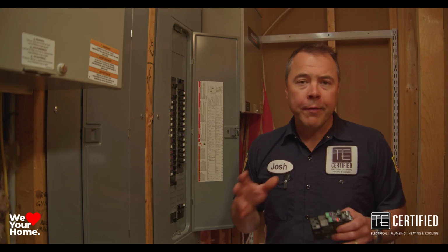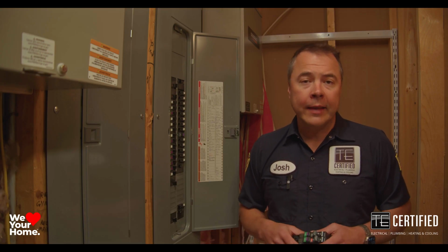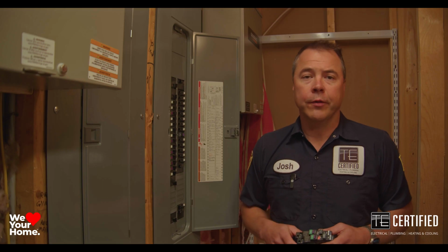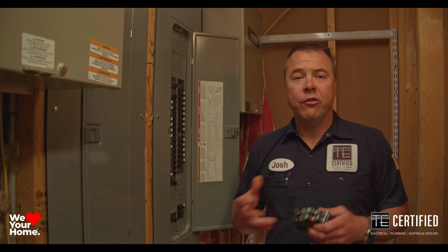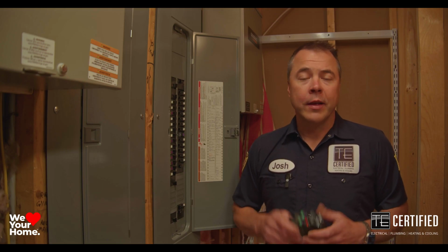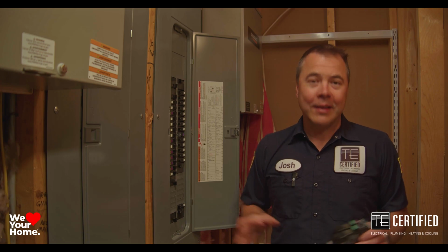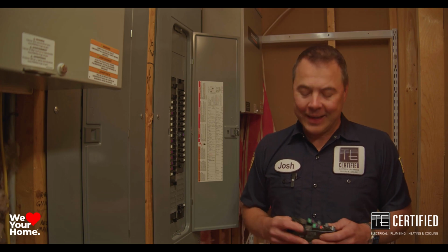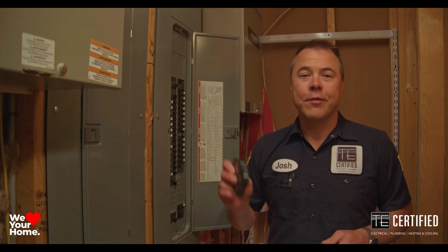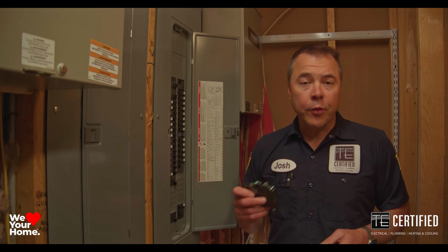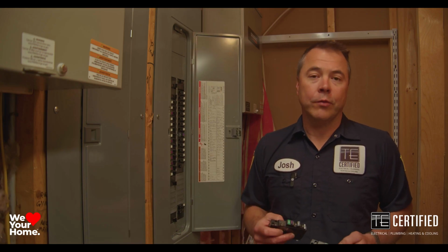We're at my house talking about electrical panels and breakers. And one of the very cool products that we install here at TE is dual function breakers. These are arc fault and GFI circuit interrupters combined into a breaker. I know that sounds like a lot, but basically it's like having a little electrician inside of your breaker that detects if you have a problem with your electrical system and instantly turns off.